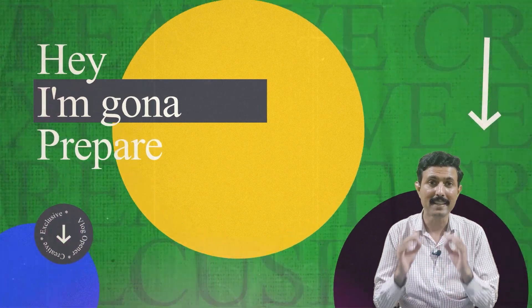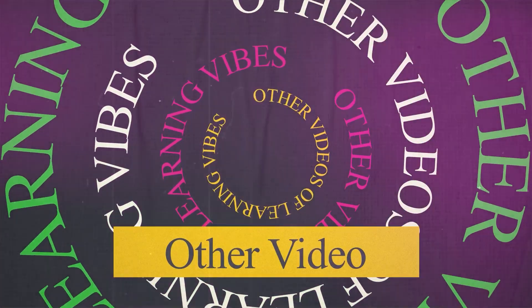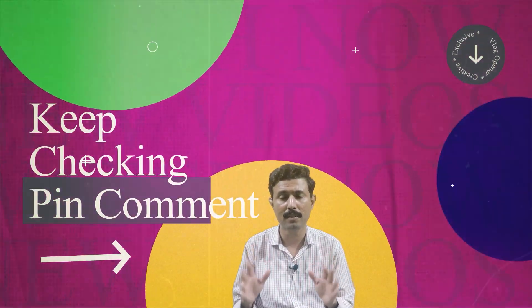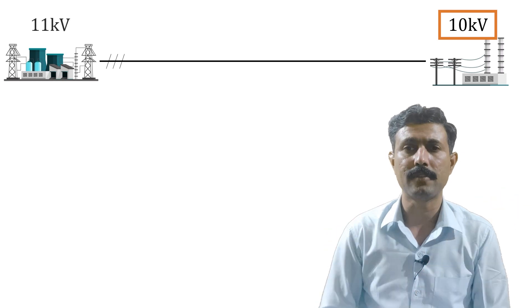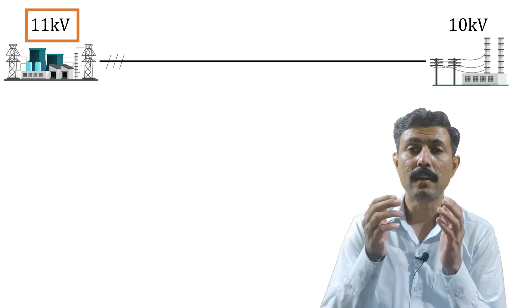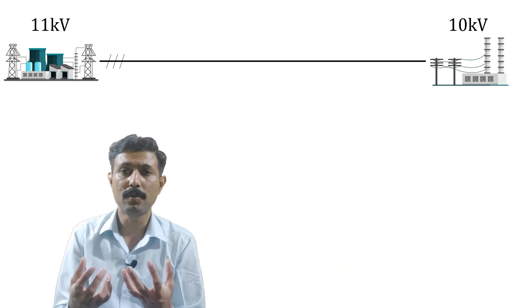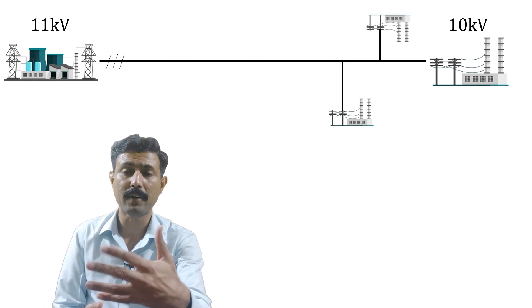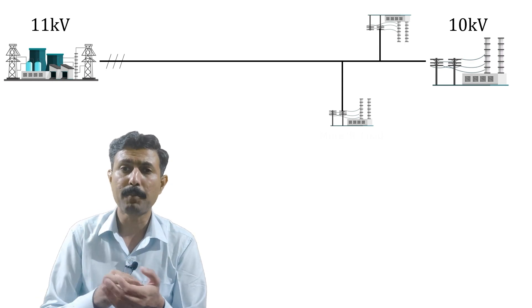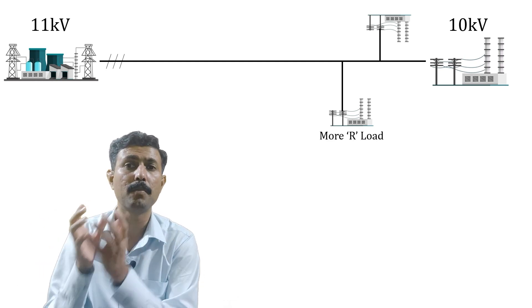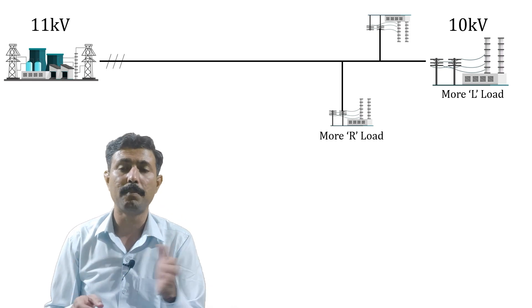You can see in this example that at the load end we are getting 10 kV, and we are sending 11 kV from the power station side. But the load is not only lumped at one place — the load is distributed. Some load is 50 km away, some is 55 km away, some is 65 km away. Also, the type of load is varying: somewhere more resistive load, somewhere more inductive load. If more inductive load, then voltage drop would be higher. If more resistive load, then voltage drop will be less.